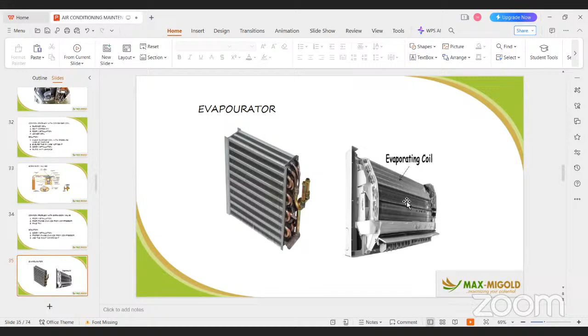Common problem with the evaporator: blocked coil. If your coil is blocked due to dust, you might be indoors, and after about 2-3 years you have not touched your AC. If you finally open it, you will see ice forming on your AC. It's because it has accumulated so much dust. The hot air that is supposed to pass through cannot pass through. So the cooling inside the refrigerant keeps cooling the surface of the fan, and the temperature keeps dropping until water on the surface forms into ice. So what causes ice, you might want to ask? It is poor maintenance culture that causes ice to form.